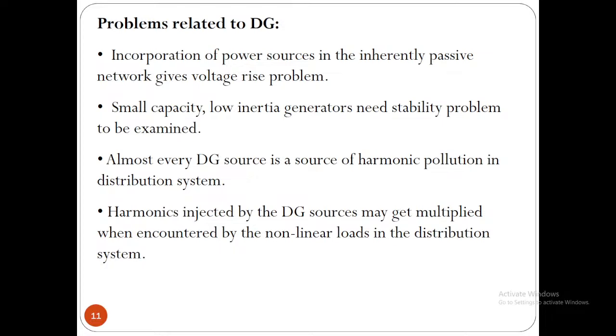And some private operators, as you know, charge for their power as they feed into the grid. I should not say this, but this is part of the commercial policy of the private player. They feed their power in a massive way, and as a result there will be enormous voltage rise if there is no control, because they are charged as per their feeding. So they will always try to feed the maximum of their power. That is the problem. Then the inertia problem is there.